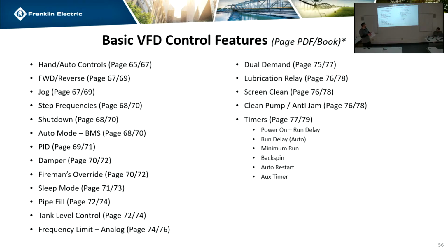Oh, frequency limits. So this is page 76. This is tied to the analog signals. You can go in and have the drive limit the max frequency based on an analog level. We use this more if you have two transducers. You can have one running a PID and one that's just there to look at the analog signal. People have it on the vacuum side and pressure side. So if the vacuum side gets too high, it'll lower the max frequency of the drive and still be able to maintain pressure. So you can set up frequency limits with analog.